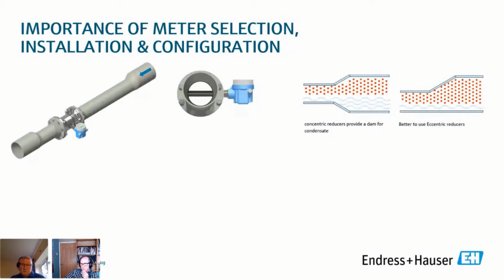It is, and if you've got this type of installation using concentric reducers, then some of this water can impinge on the sensors, and it can affect the turn down, affect the measurement accuracy, and cause you massive problems in the steam system.